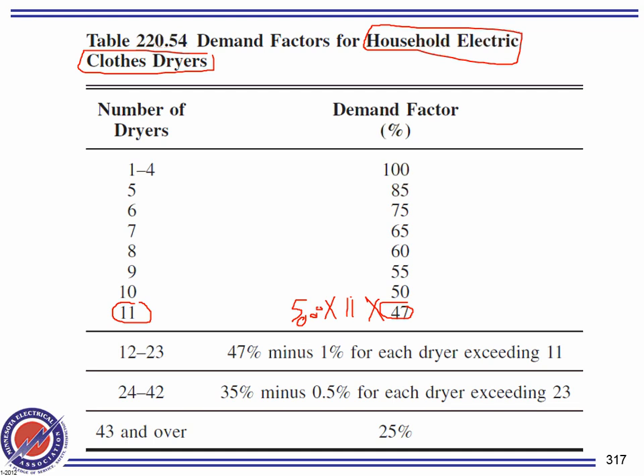For the service that feeds these apartments. Am I making sense? Don't forget the 5,000. Now, what happens if your number is 20 here? Then you have to do funky math, right? Let's do this funky math. It says 47, minus one percentage for every dryer exceeding 11. So 20 minus 11.